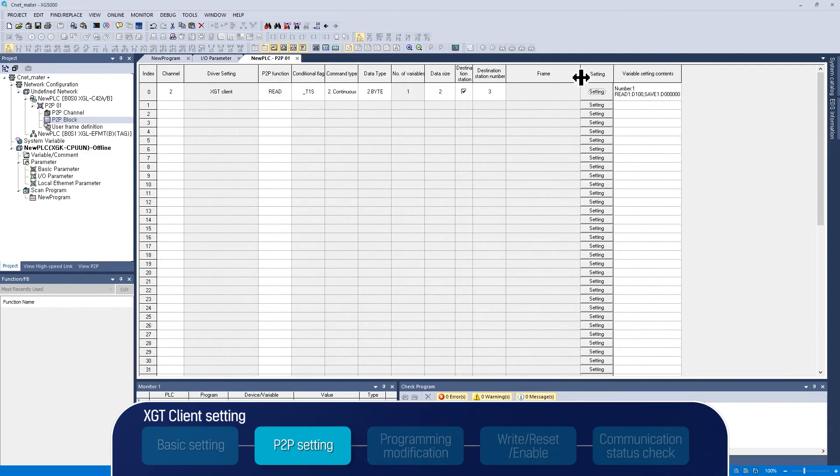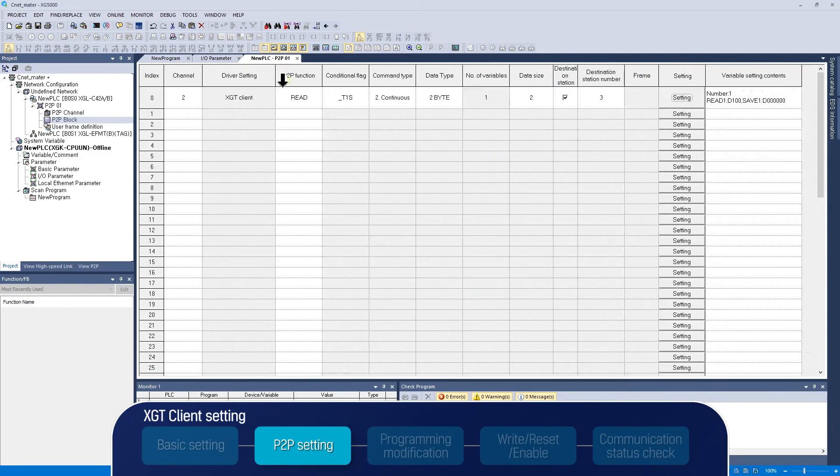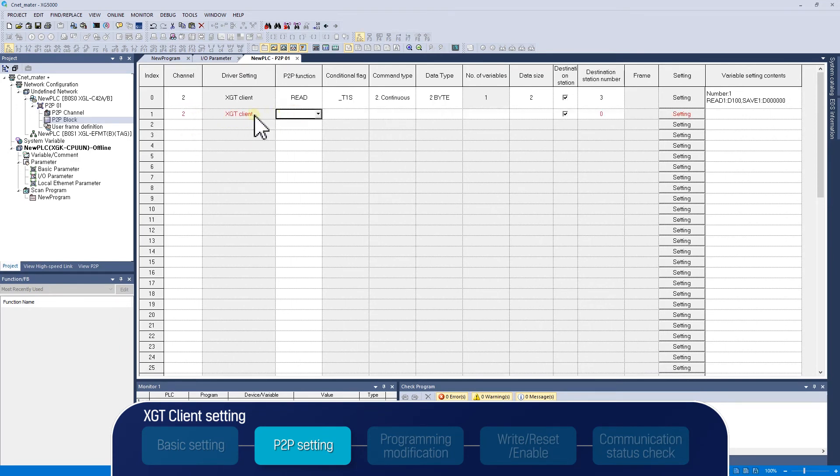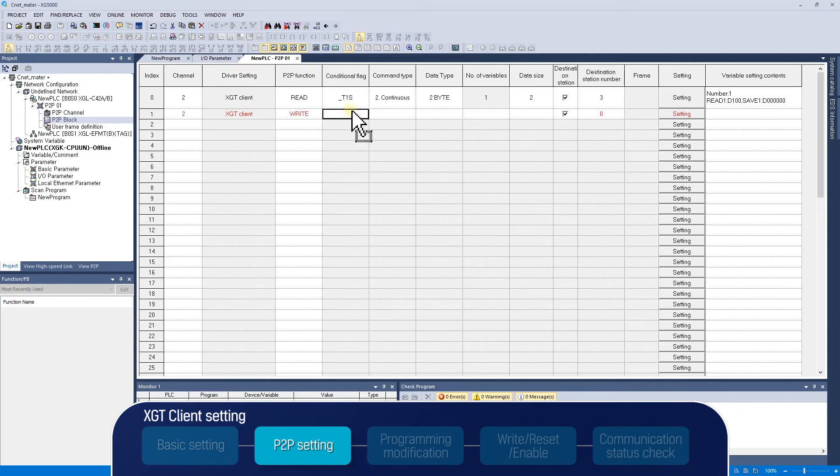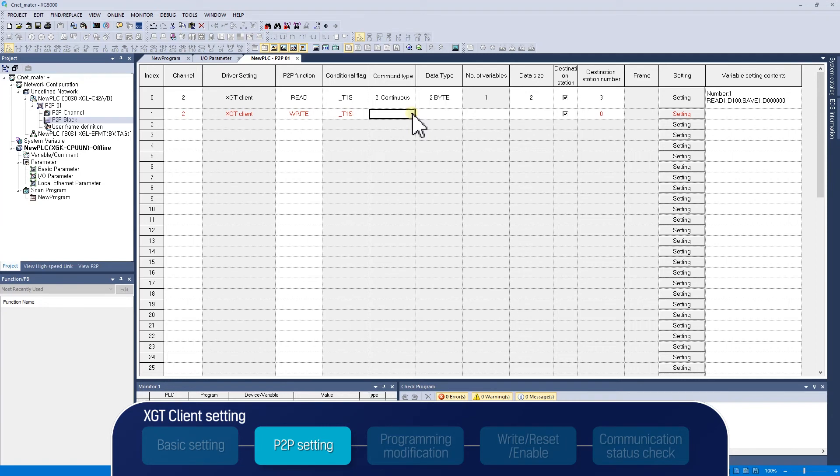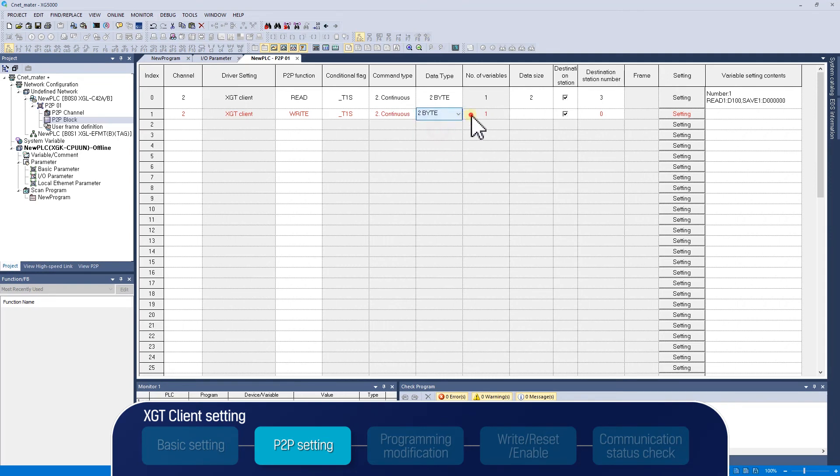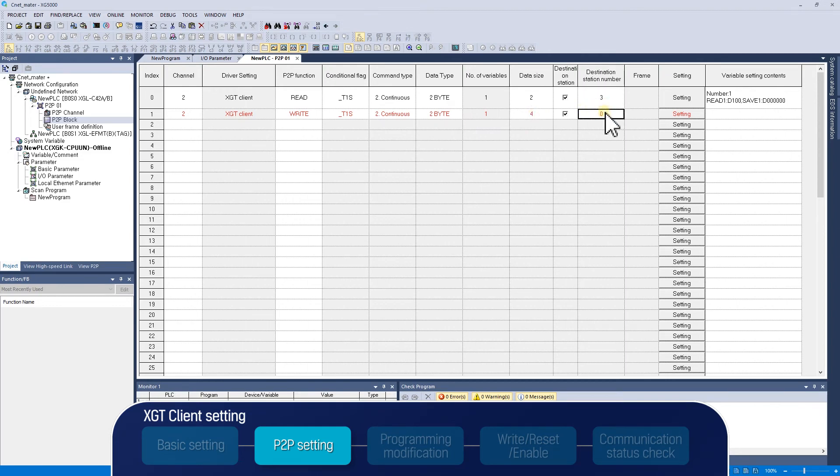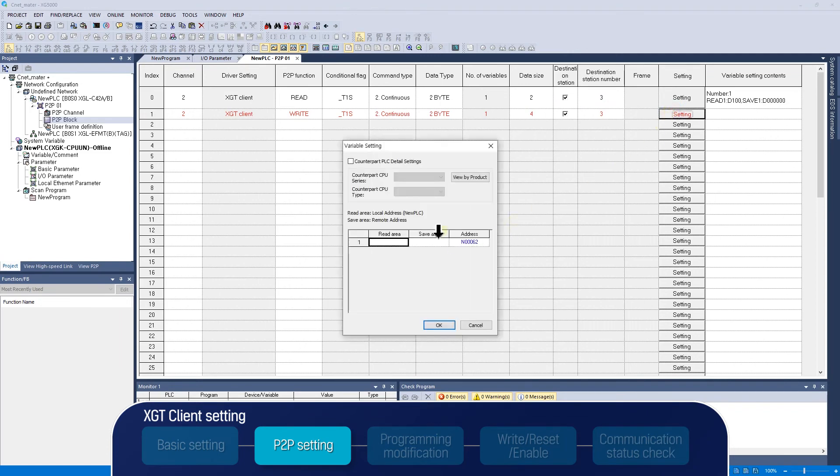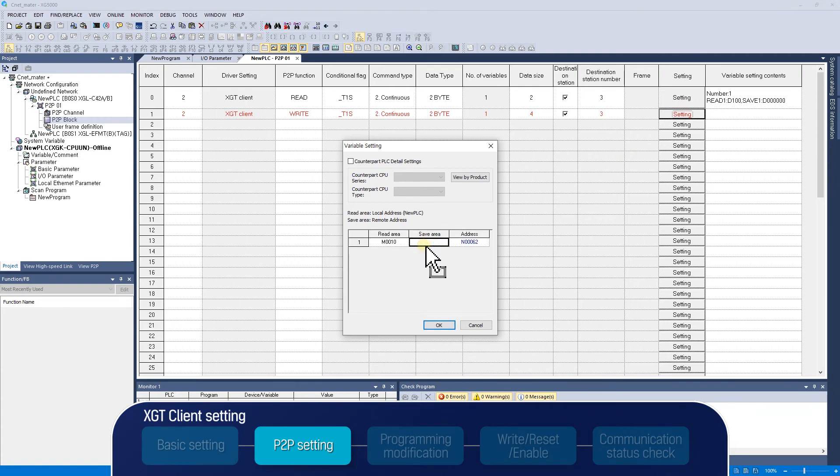Let's make a write request in index 1. Selecting 2 in channel, XGT client driver will appear in driver setting. Select write in P2P function and enter F93 bit, one second clock flag, in conditional flag. We will write forward data to target station 3. Select continuous in command type, 2 byte in data type, and enter 4 in data size, and 3 in destination station number. In case of a write request, data transfers from my PLC area to the target station memory. Different from index 0 setting, read area is the memory of a destination station, and save area is my PLC memory.